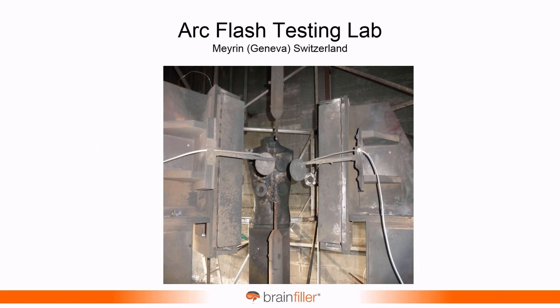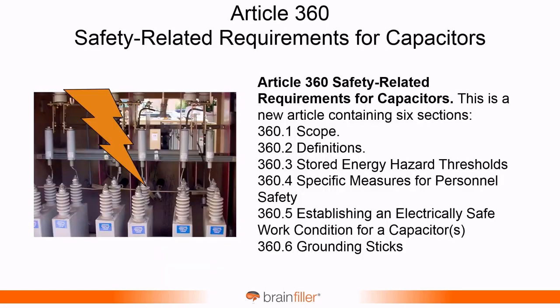And in fact, this is the test setup. This was in Geneva, Switzerland. I was there recently. And if you look at the test setup, there's a couple of labs that will do this. The big one is actually in Canada. There's a lot of testing there. So this is a calorimeter that measures the energy, and then you have opposing electrodes where you put a trigger wire, and then that initiates the arc flash right there. And then you have the fabric samples of the garments on the panels that are spread equidistant around there.